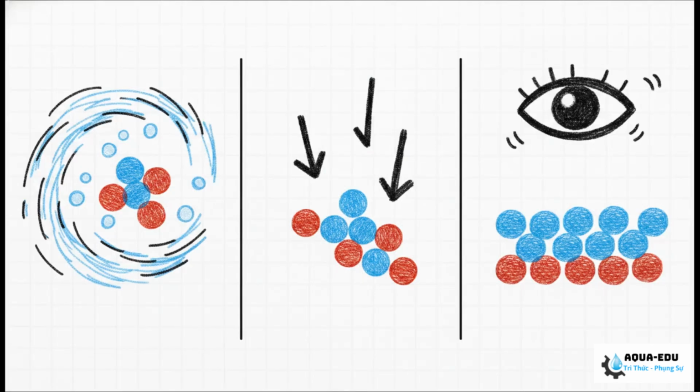Now, if your core sample showed that foulants have artificially bumped up the resin density by sticking everything together, a normal backwash just won't cut it. An extended backwash protocol is really the only way to break those clumps apart and get that natural buoyancy back. After the wash, you absolutely have to wait a few minutes for complete gravity settlement. Then, and only then, you check the sight glass to confirm that the lighter anion is resting entirely above the denser cation. Only after seeing that do you initiate your chemical draw.